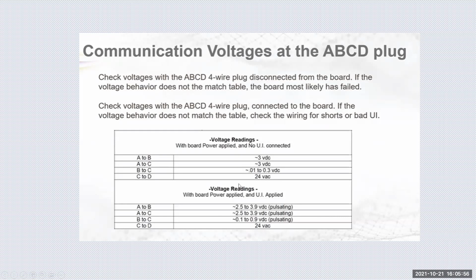Now, say we have our 3.5 outside on our wires. We're going to now go to the control board off the outdoor unit. Power applied, you should be getting 2.5 to 4 off of your control board. If your transformers and everything are good outside and you're not getting your outdoor power coming off your outdoor unit, you have a bad board, it needs to be replaced.